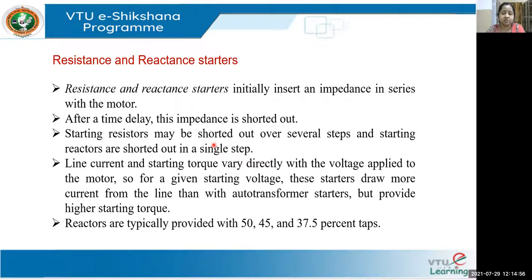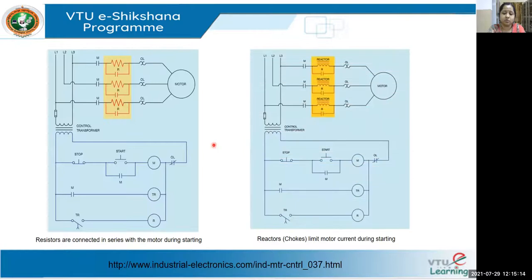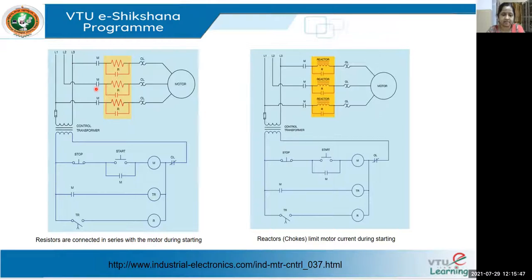There are two circuits displayed on screen — a resistance starter and a reactance starter. In this circuit, you can see your motor with resistances connected in series. The elements that look like capacitors are actually contactors. The contactor M is the main contactor, and contactor R is for the resistances connected in series with the motor and the line. The setup also has a stop button and a start button.